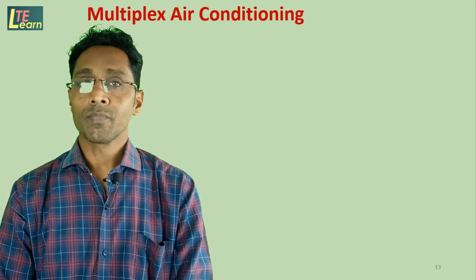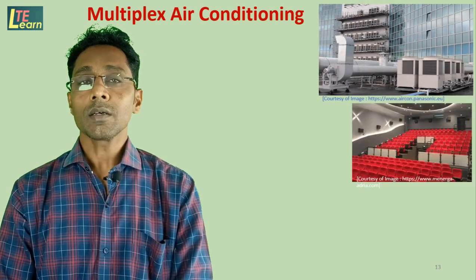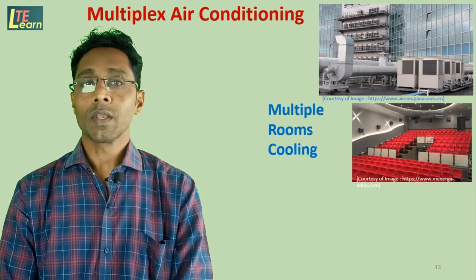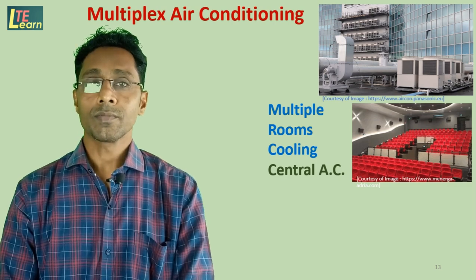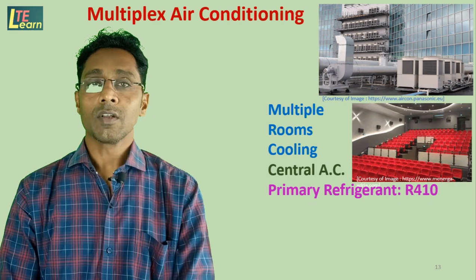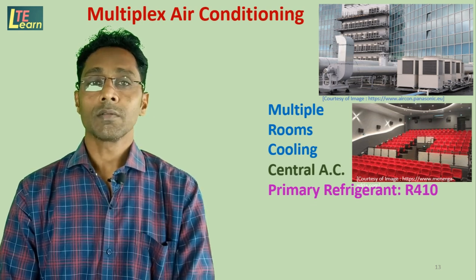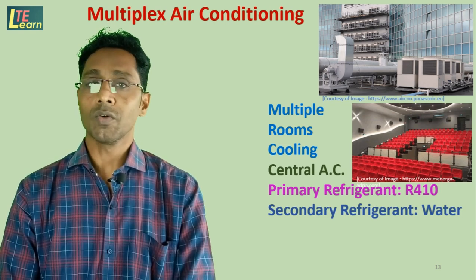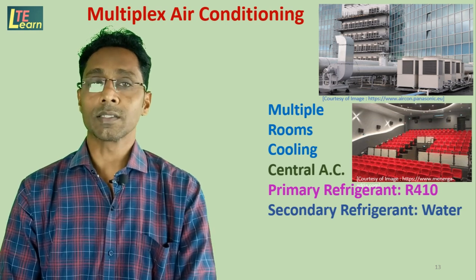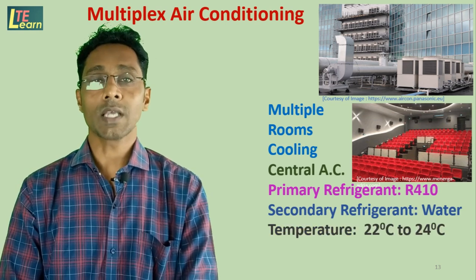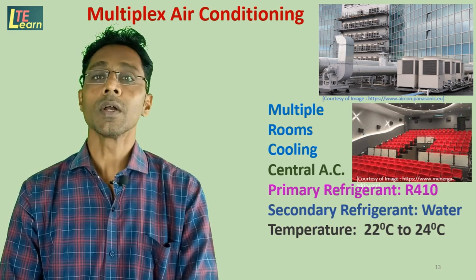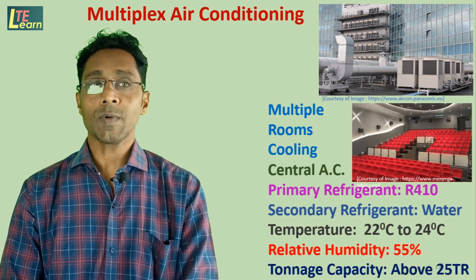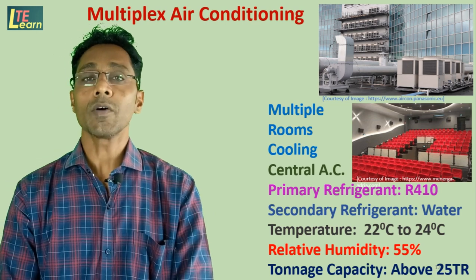Multiplex air conditioning: In a multiplex there are multiple rooms, so central air conditioning is used for cooling. Two refrigerants are used: the primary refrigerant is R410 in a VCRS, and the secondary refrigerant is chilled water at 4 degrees Celsius. Room temperature is maintained in the range of 22 to 24 degrees Celsius with relative humidity of about 55%. Tonnage capacity for multiplex air conditioning is about 25 TR.